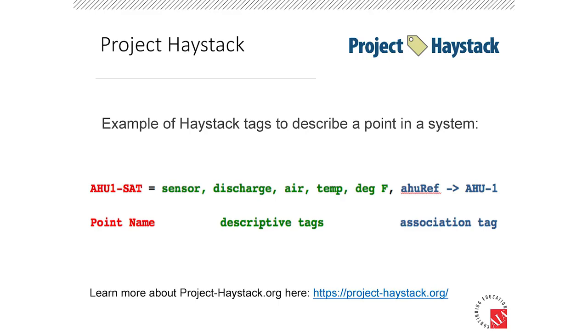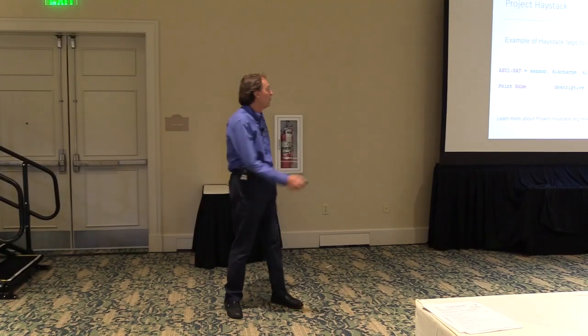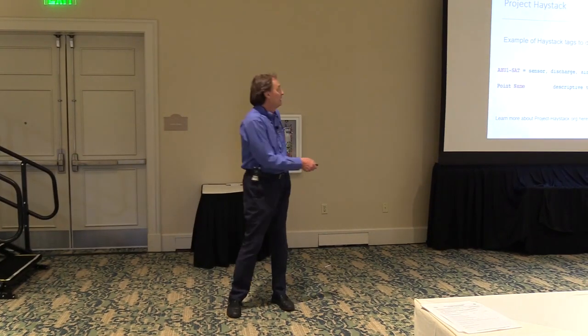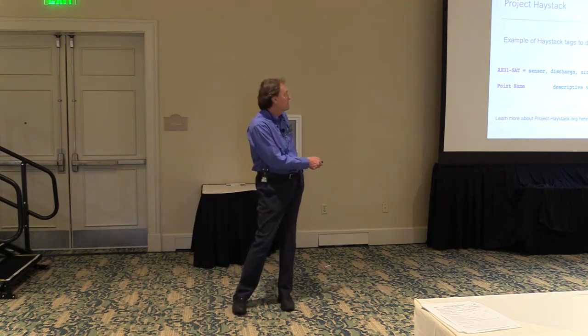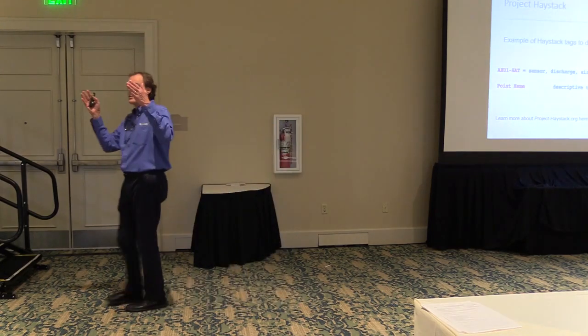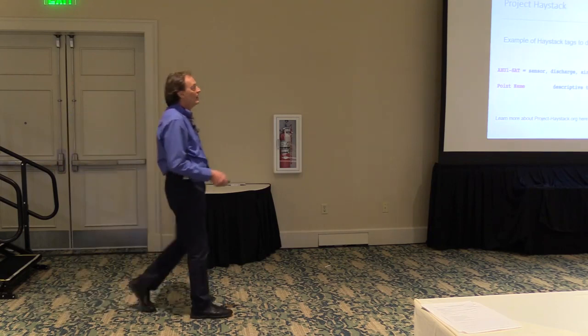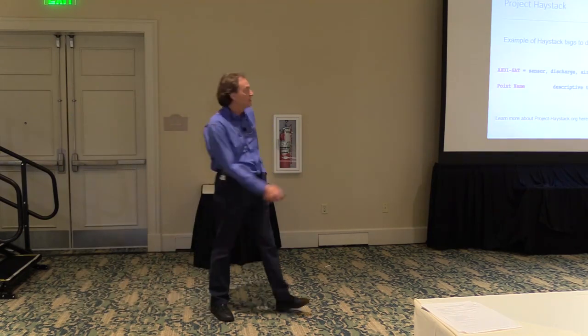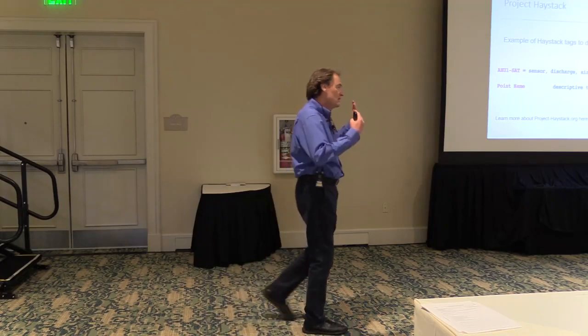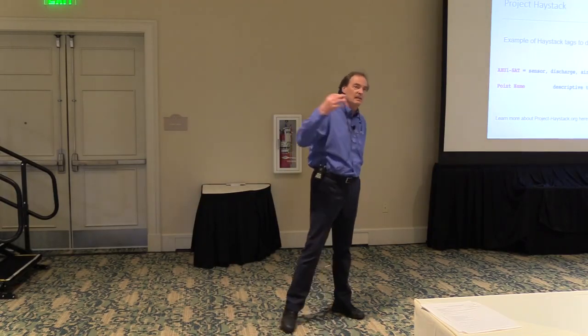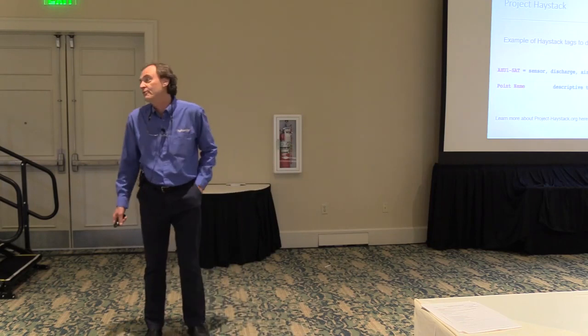But we can come up with a uniform way to say what it means. So in green, a tag says this is a sensor as opposed to an output. This is discharge, of air or water. This is air, and we're measuring temperature in degrees Fahrenheit. Those describe what it is. But then we had one other tag, an association, the air handler ref or the schedule ref, another type of tag. With those tags on a piece of data, software can automatically consume the data, analyze it, present it, and help us accomplish our end goals.